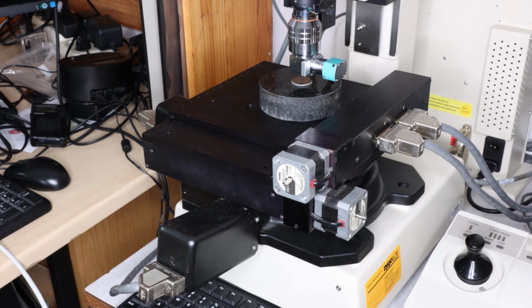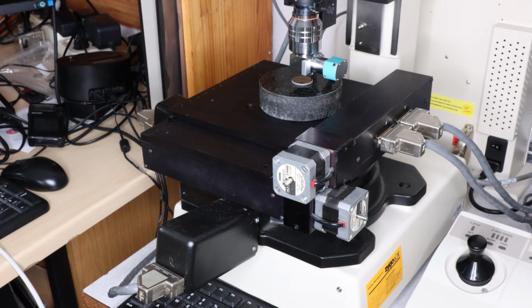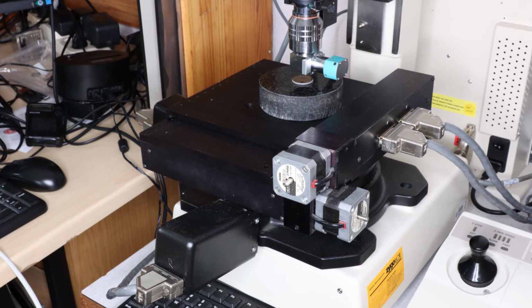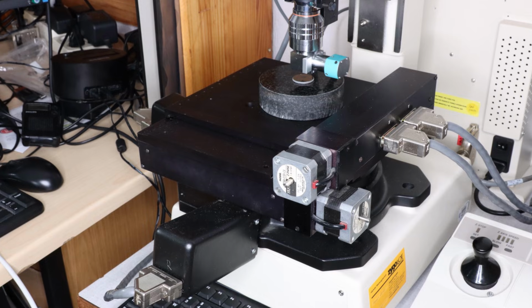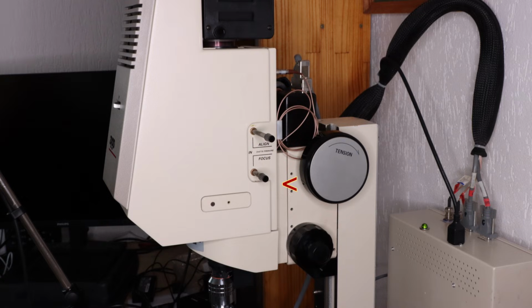Mechanically, it's a fully motorized 5-axis system. It contains a large 4-axis stage for translation and tilt over the X and Y axes. Then there is the 5th axis, which is the translation along the Z axis, so the axis that does the actual scanning perpendicular to the surface. The Z position can be set with different degrees of accuracy.